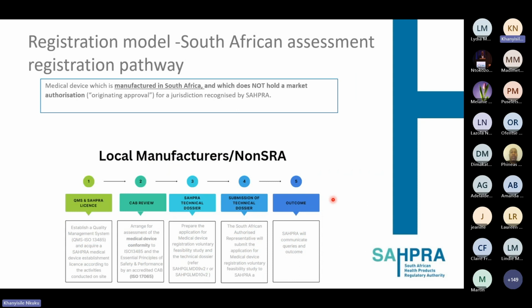For the registration model that looks at the South African assessment part, this is for medical devices manufactured in South Africa, or those that do not hold market authorization from a jurisdiction mentioned in the previous slide. The process for these as well requires that they establish a quality management system according to ISO 13485, and ensure they have a medical device license with the products listed on their license.